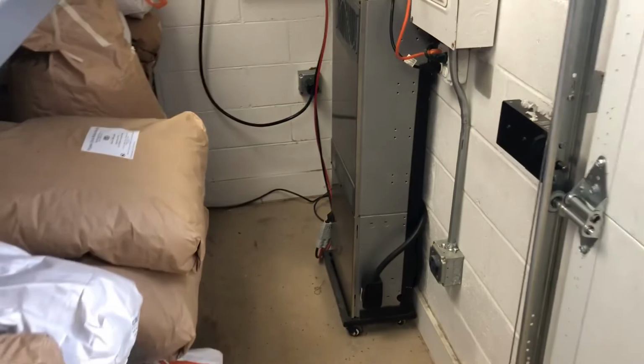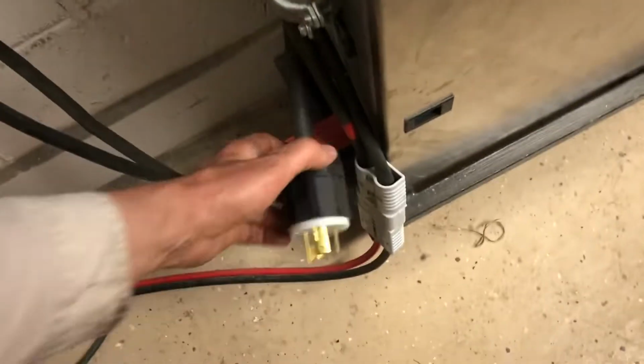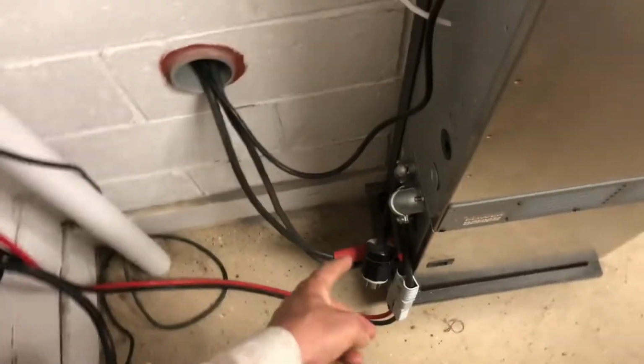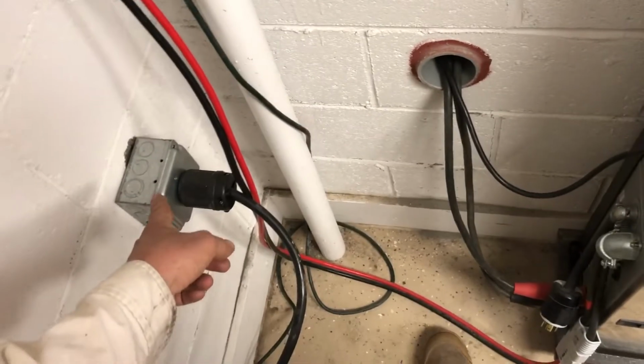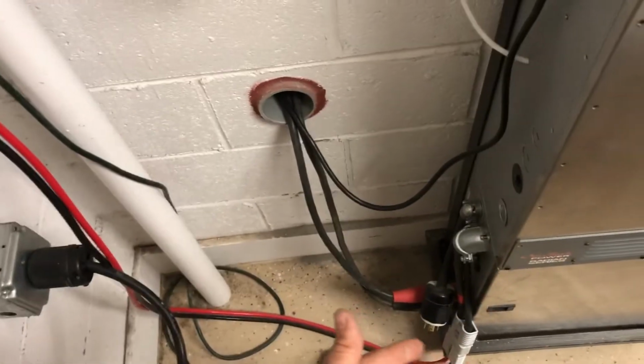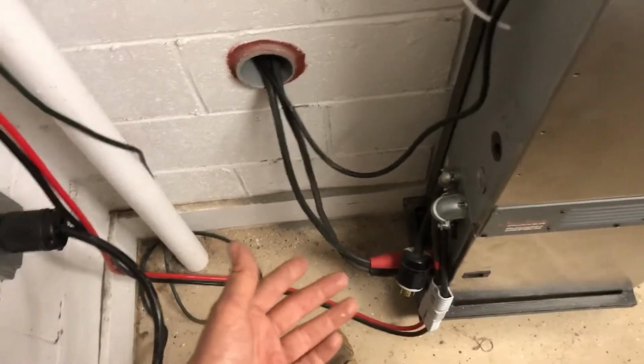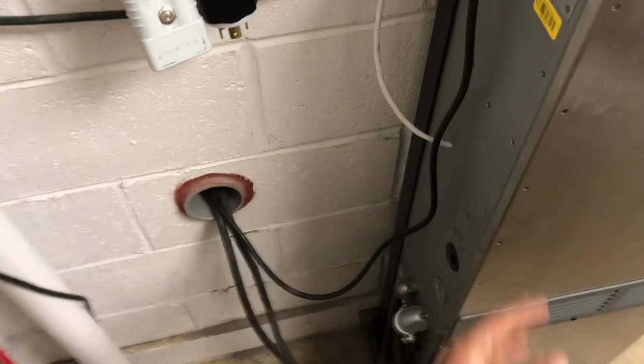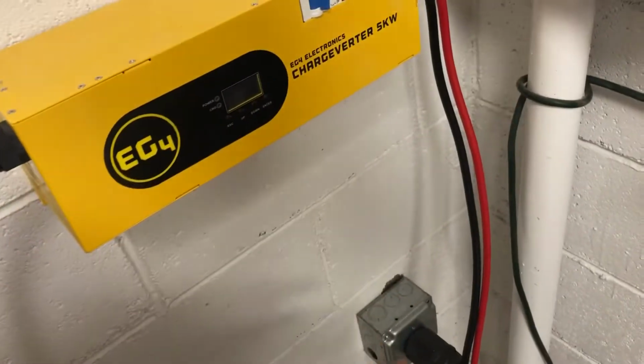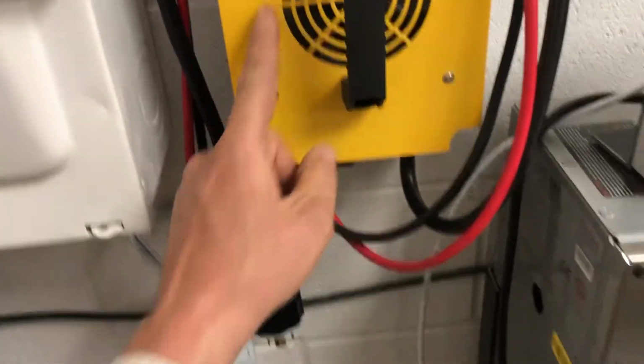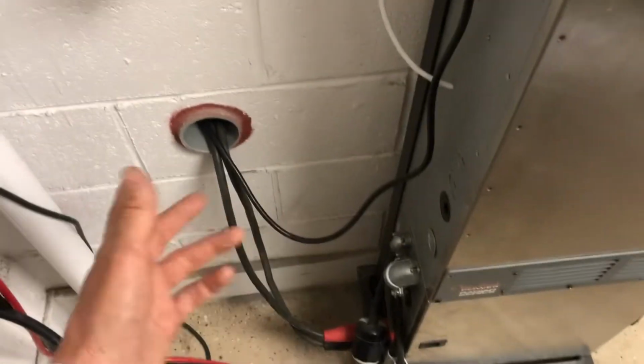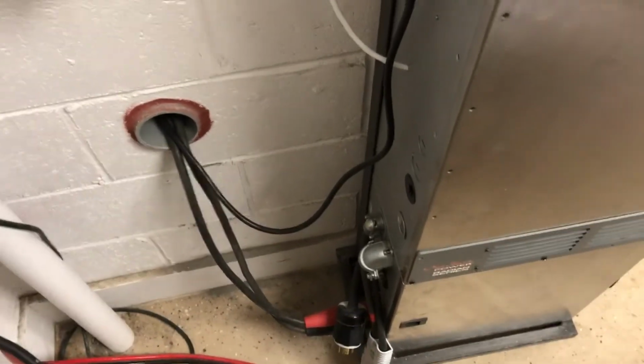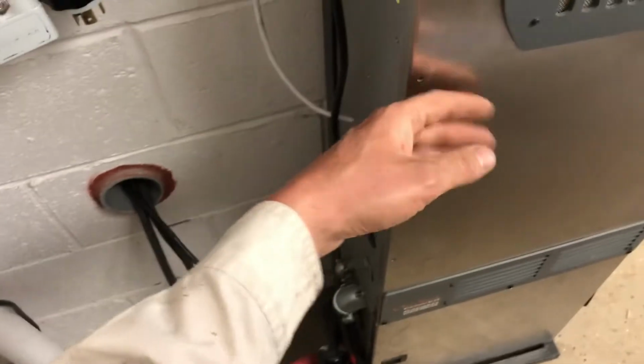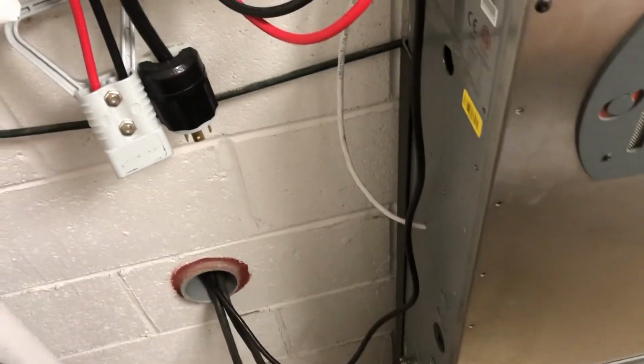Hang on, let me get the lights back. They're a motion sensor. This inverter has a 30 amp connection to the grid, so you can plug the inverter into here and charge the batteries. You wouldn't be able to use AC loads though, using the onboard charger, or you could plug this into there and use that, or you could use the backup, or in their case you could plug the generator directly into the inverter and use the inverter's onboard charger to recover the batteries.